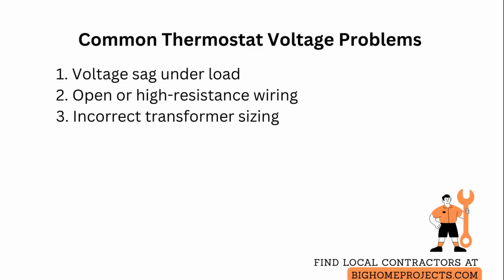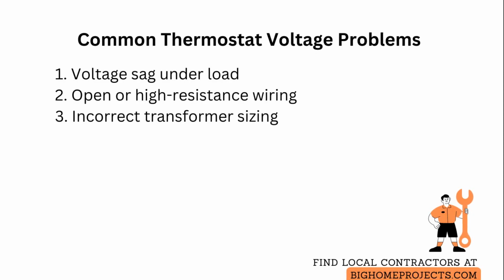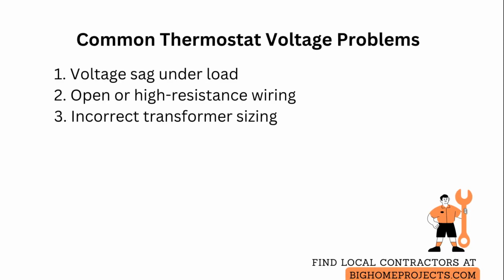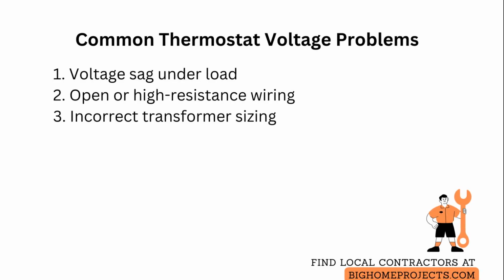For incorrect transformer ratings, confirm the transformer secondary amperage meets the total control circuit demand. If adding accessories, calculate total milliampere draw and choose a transformer with at least 20% higher capacity.